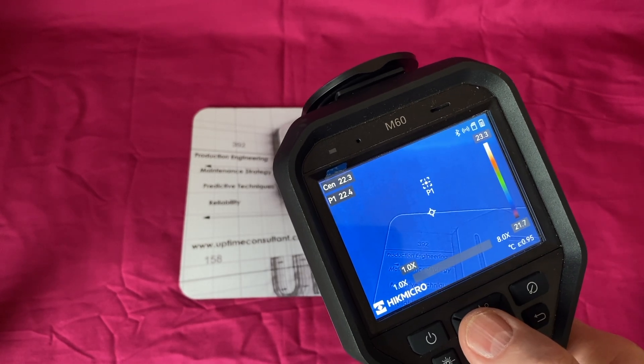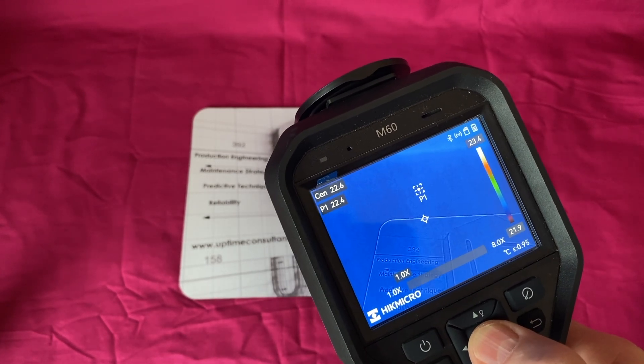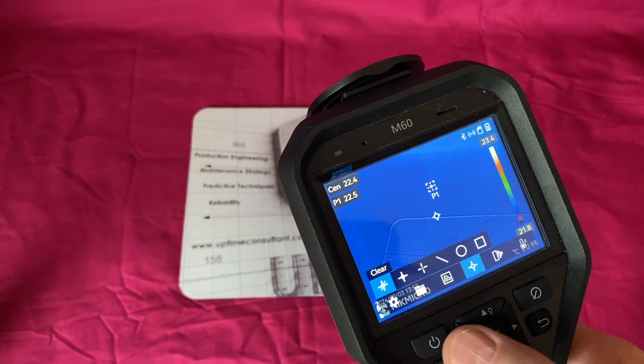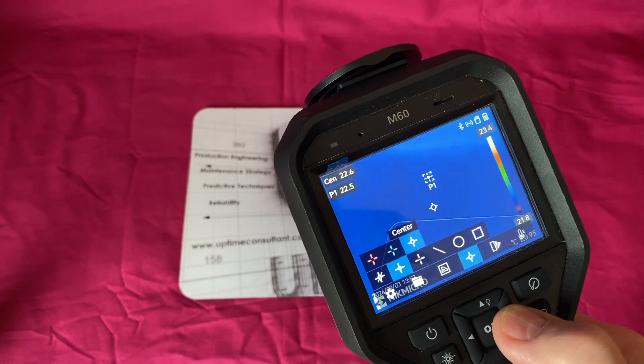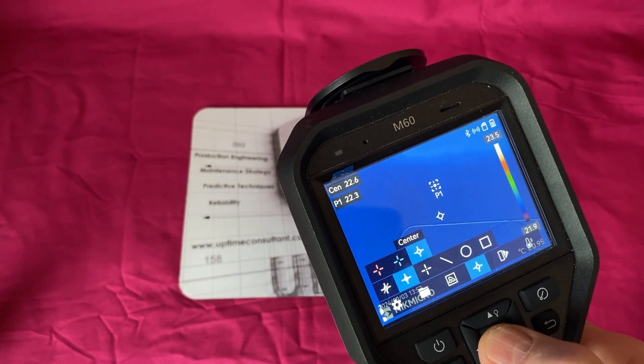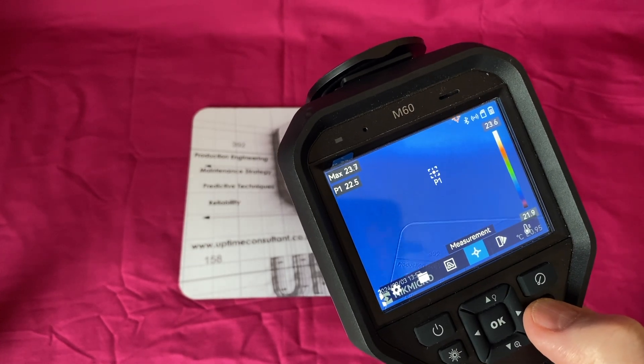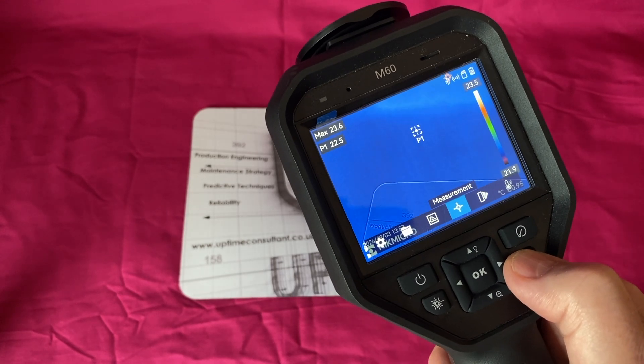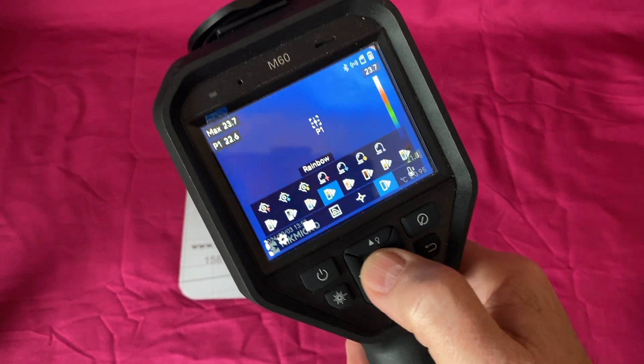At the moment we've got a point measurement and a central spot - both reading 22 degrees, which is the room temperature. We can put a measurement point on; the last option is to clear. We can put a hot spot, cold spot, or center spot in. The center spot is on - press it and it goes off, press it again and it comes back on. Let's put a hot spot in - you can see that hot spot is actually tracking up the top there, because behind that cover is my iMac on standby, so it's tracking something warm behind that cover.